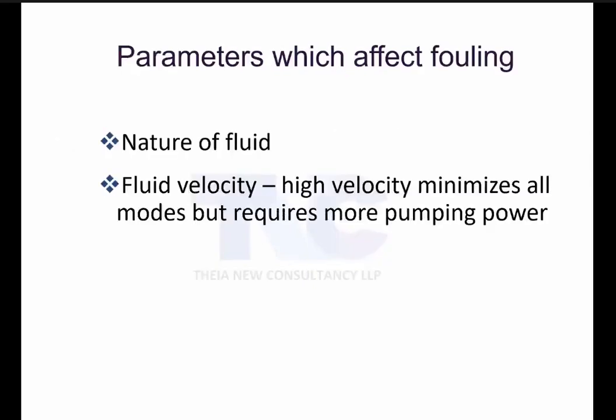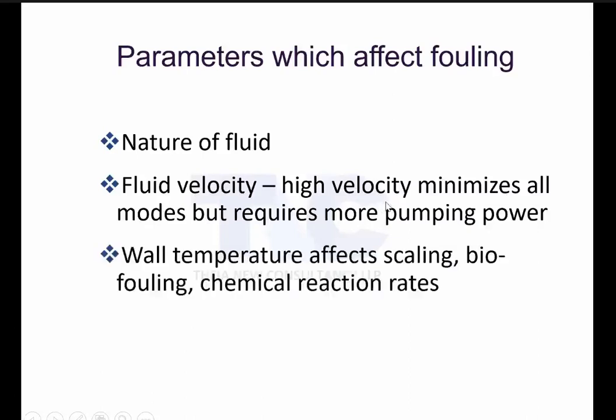So the fundamental thing causing the fouling is the nature of the fluid. What type of fluid you're using, that is the major cause of fouling. Then the contributing cause is velocity. This is where I said in the beginning, for liquid you need to have 3 to 5 feet per second. All these things come because of this. When you have low velocity, you generally have more corrosion, more fouling. When you have high velocity, it will minimize some fouling.